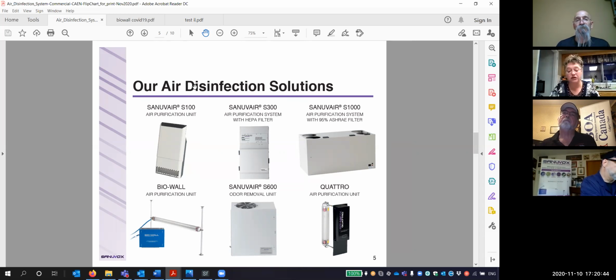And so we calculate out things that are important. We need to know the CFM, we need to know the duct dimensions, we figure out the velocity. We need to know the material of the ductwork. And these are all things that affect how we size out the equipment. All commercial jobs are sized out independently. There's no commercial job that's identical. So we have 2 different solutions for air disinfection. We can do a standalone unit that will do a room, or we can do a duct system.